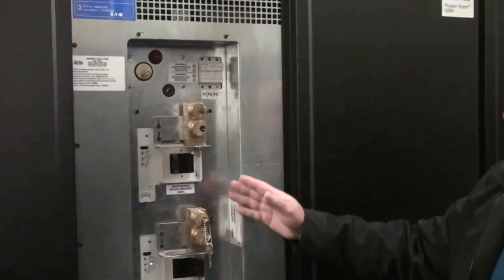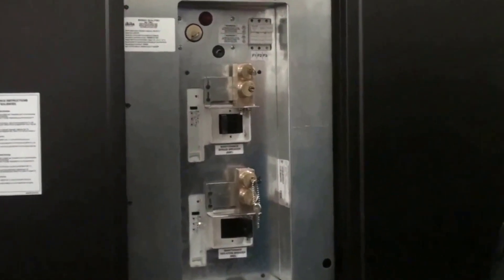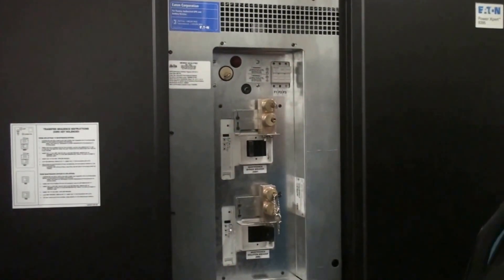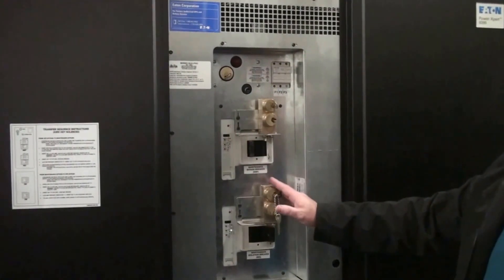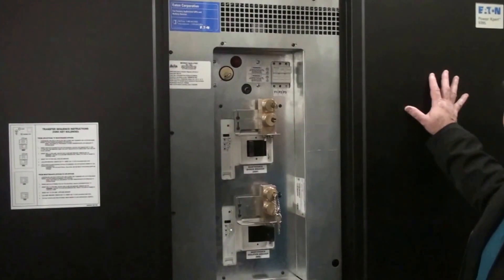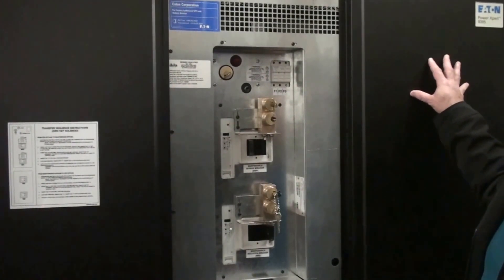The UPS bypass — it's a Kirk Key system. In essence, the UPS would be placed into static bypass. Once it was in static bypass, you would utilize this to lock it out, bypassing the electricity around the cabinet so that you could do maintenance on the UPS.